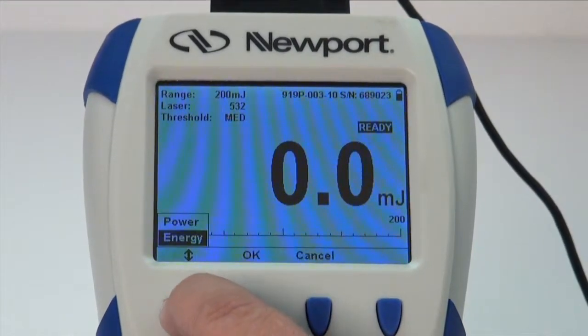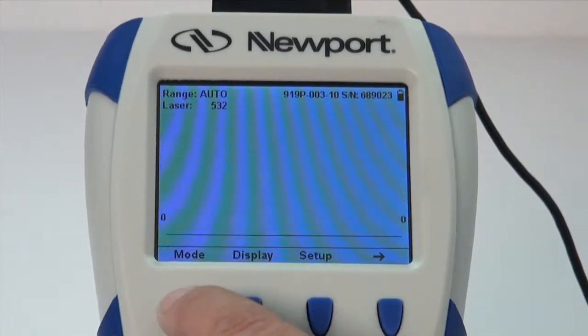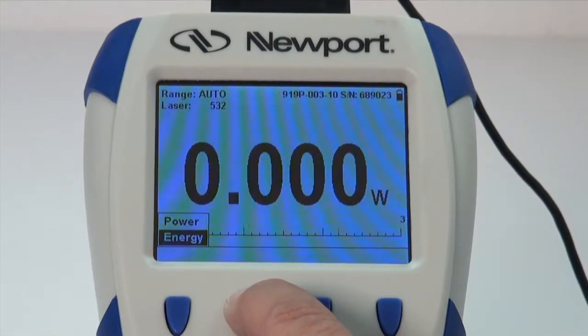Use the mode button and the down arrow to select the measurement type. For a pulsed energy measurement with a thermopile detector, select Energy, then press OK.